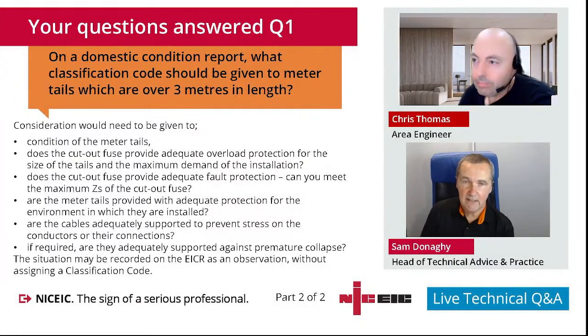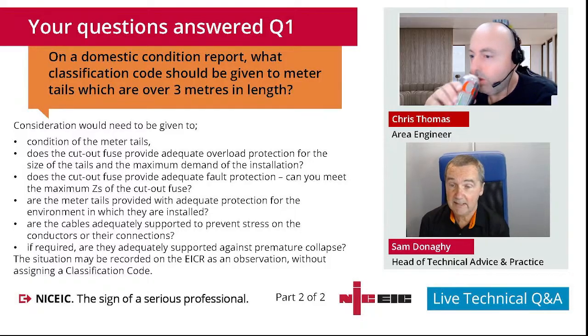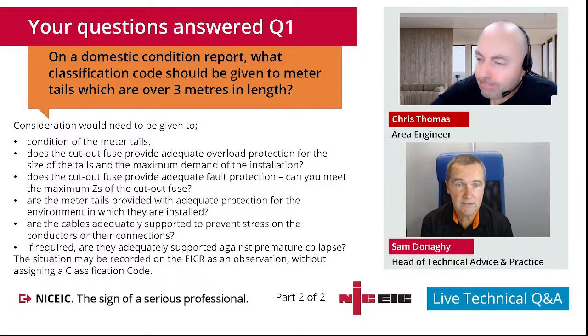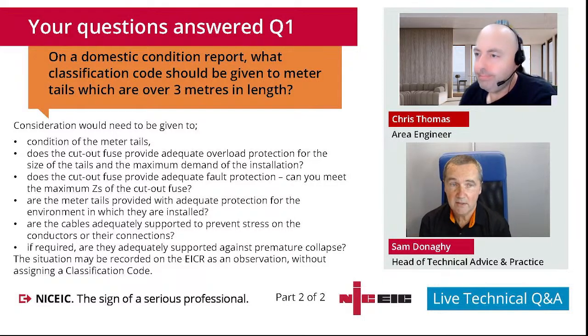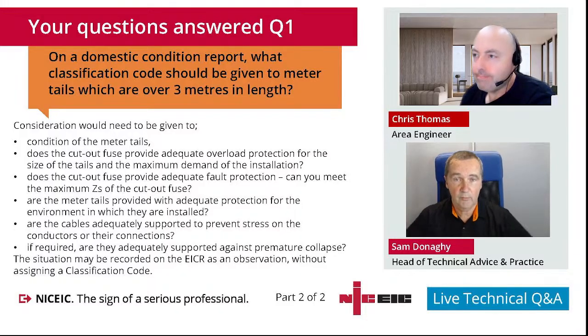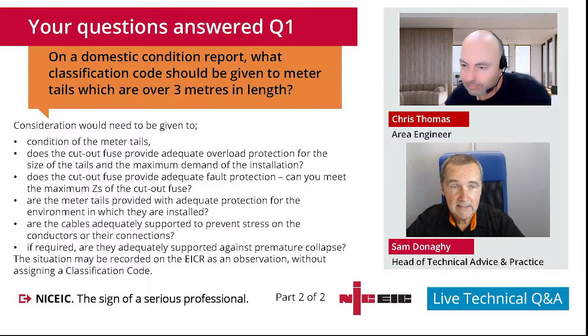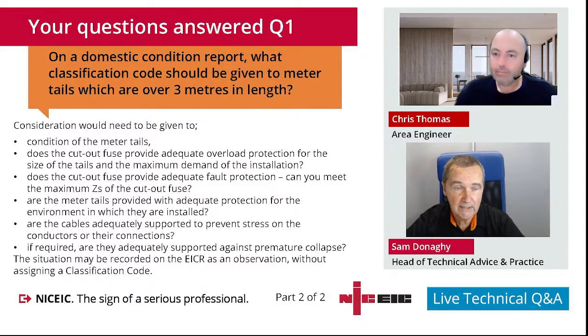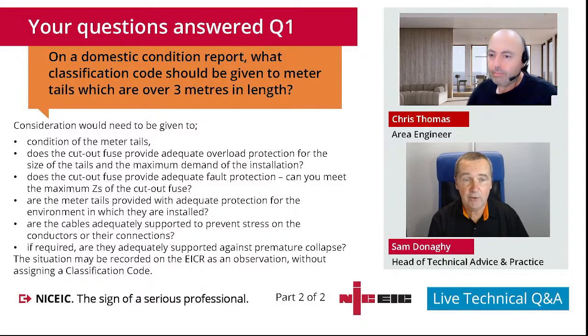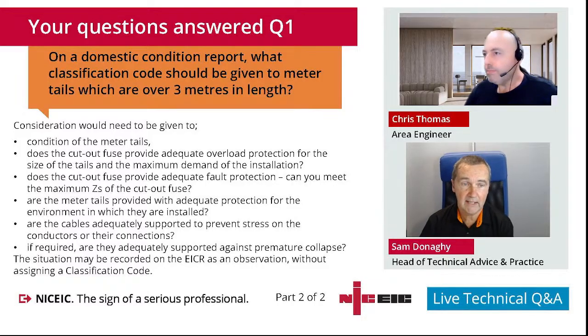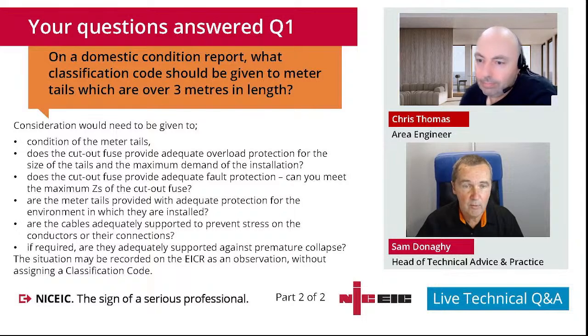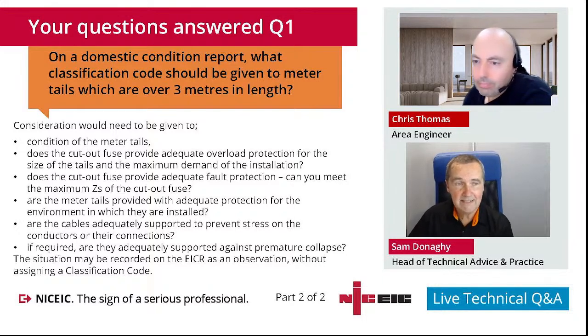We would still suggest that there are some things that you would need to look at. So the condition of the meter tails, are they still fit for purpose and safe to use? Is the cut-out fuse adequately sized for the size of the meter tails so that it will protect against overcurrent? Does the cut-out fuse provide adequate fault protection? Are the meter tails provided with adequate mechanical protection for the environment in which they're installed? Are they supported so that there's no stress on the conductors or the connections? And if required, are they adequately supported against premature collapse? So all of those things need to be considered, but purely because of the length, it doesn't create an unsafe situation. But if any of the above things came into it, that could result in them being considered unsafe.